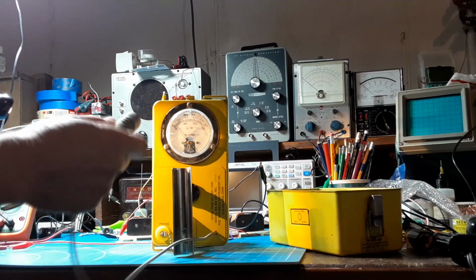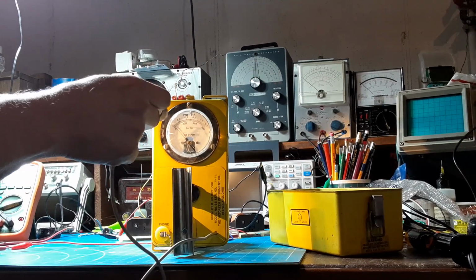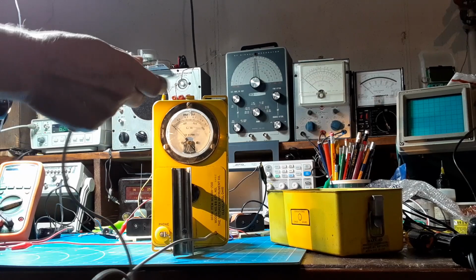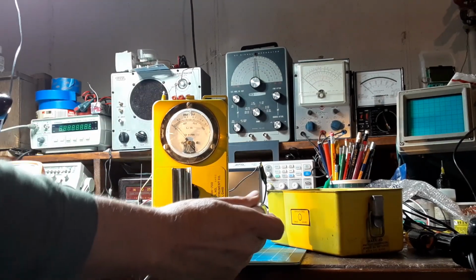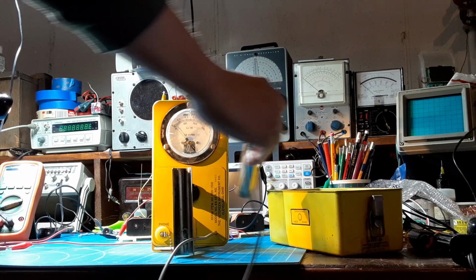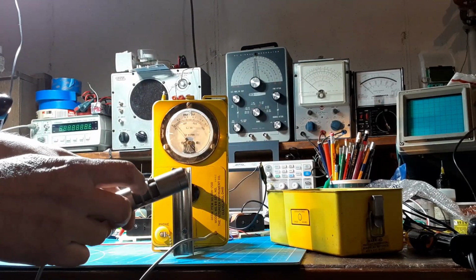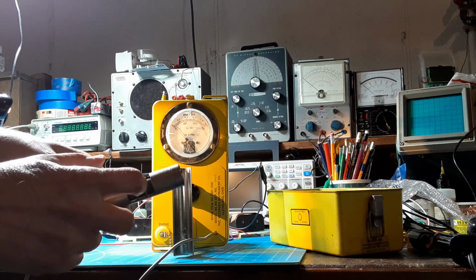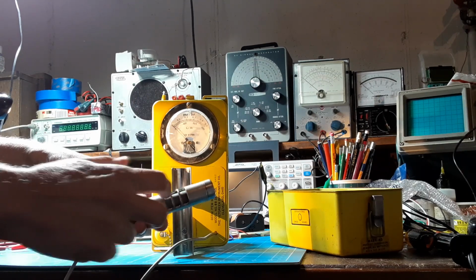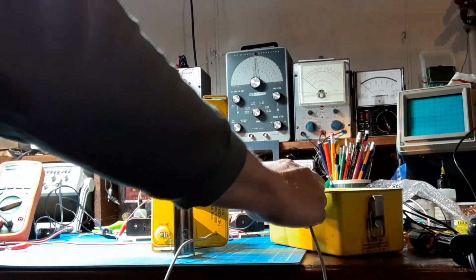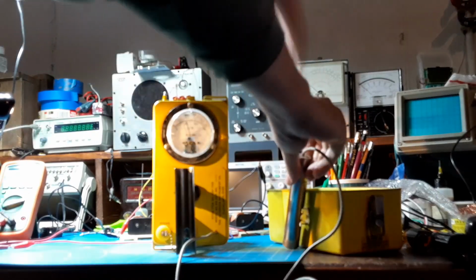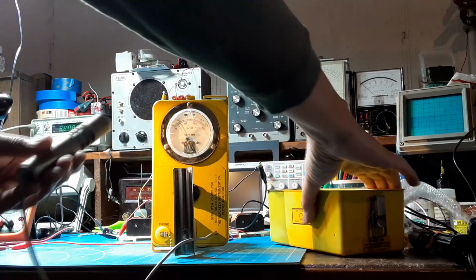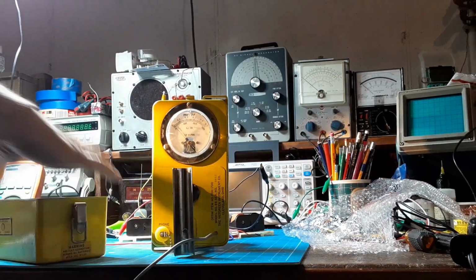And you put it on 10, you should get, I mean right now I'm getting normal ground noise, ground radiation. Should get around 0.2, or well 2 because it's times 10 MR per hour. What you do is you got to put the dot there in one of these. Actually, the center one's the best, and it needs to be in between the metal plate so you get an accurate reading. So if we put that directly there, I'm trying to stay out of the way of the camera. I don't think I'm doing a good job of that. Let me move it over here. You just have to take my word for it.